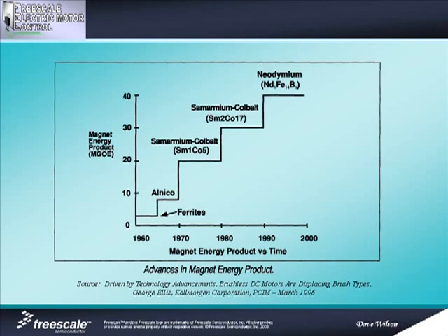You really have to be careful when you're working with neomagnets. In fact, these magnets are so strong that something as simple as manually inserting a rotor with neomagnets on it inside of a motor frame can be very dangerous. It turns out that the attraction force increases dramatically as these two pieces come closer together. And some customers have even reported incidents of personal injury as the rotor gets sucked inside of the stator frame.